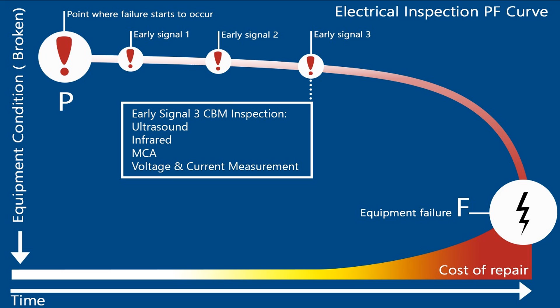Now what stage 3 will show us is motor current analysis, voltage and current measurements. All these readings are going to start to increase significantly, way outside of acceptable alarm levels.